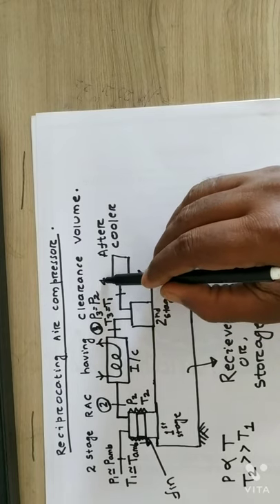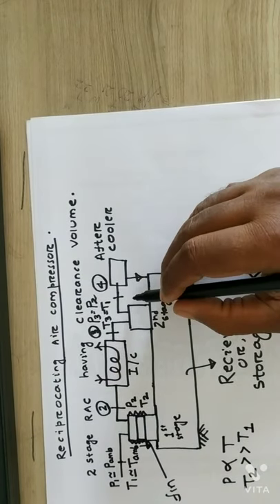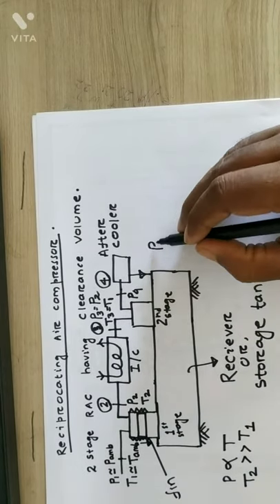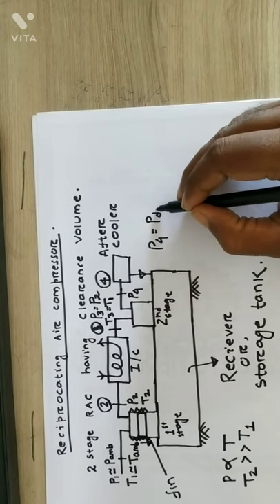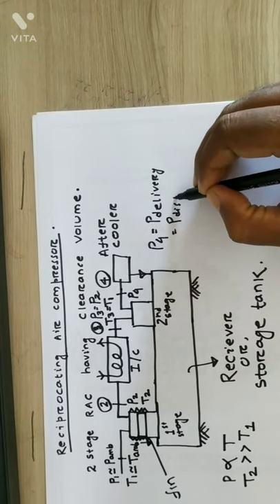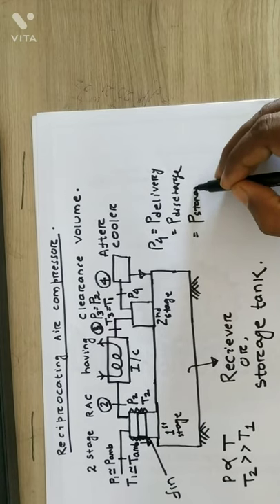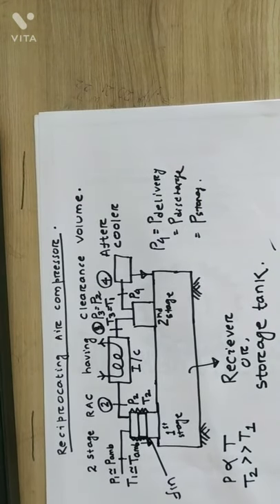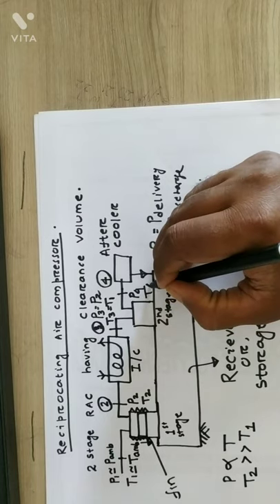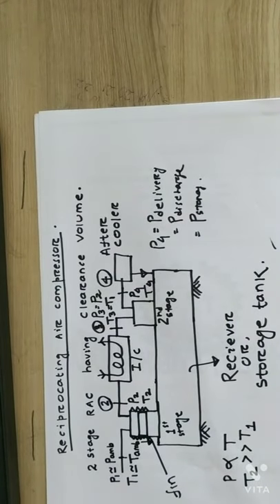State point 4 is after the second stage compressor. The pressure P4 equals the delivery pressure, also called discharge pressure or storage tank pressure — this is the pressure at which air is stored in the tank. There will also be a rise in temperature T4, but an aftercooler arrangement reduces that temperature. This completes the entire block diagram.